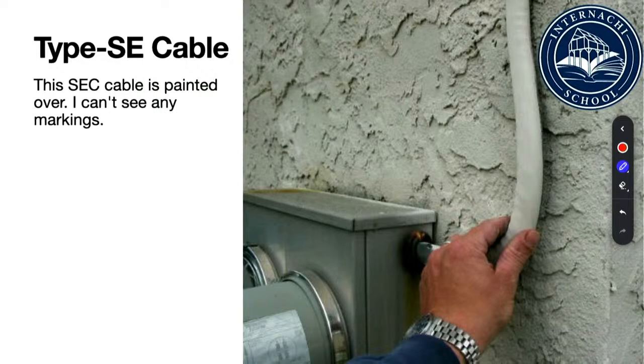It's nice to be able to read these cables so that you can determine how big the conductors are inside of them. I guess you could take a guess at it, but for me, and I'm going to show a slide in a little bit, there's really 5 things you need to know to properly determine the amount of amperage and if it's safe. Number 1, which we do have to document in the SOP, is the main disconnect rating or whatever's printed on there. But we also need to know the size of the wire, the rating of the meter panel, the rating of the disconnect panel that comes in there. We mentioned the wire itself along with that breaker that we mentioned at the very beginning.